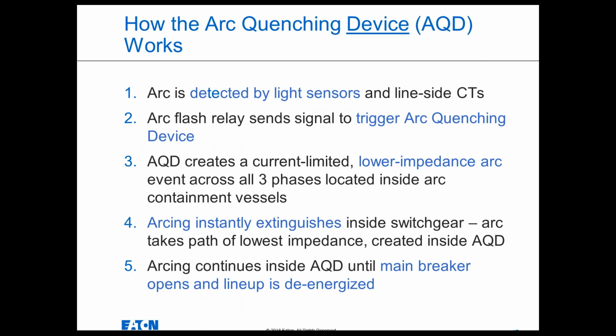So obviously the question here is, how does the arc quenching device work? Light detection systems are pretty well understood. So really the interesting part here is actually what's happening inside that arc quenching device in that very short period of time when it's told to activate by the arc detection relay. So that arc light is detected by the light sensors and line side CTs. That relay sends the trigger signal to the arc quenching device. And then what the arc quenching device does is it creates a current limited, right? Not a bolted fault, not a crowbar. It introduces some impedance, a current limited, lower impedance arc. Essentially what it does is it creates a path of lower impedance, because current always follows the path of lowest impedance, event across all 3 phases located inside arc containment vessels.